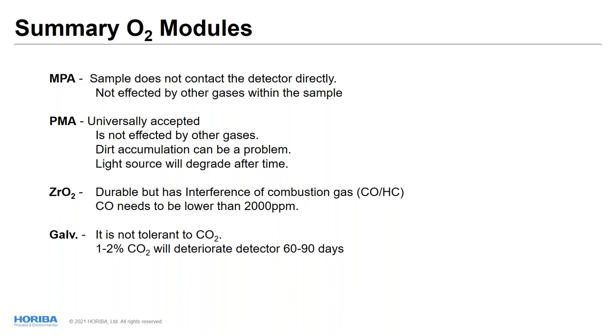The galvanic method is the lowest cost and works with a battery, so you will need to replace it periodically. It is also sensitive to CO2, and if a high concentration of CO2 exists, it will deteriorate the detector. That would be one of the weak points. So it depends on your gas composition and gas condition, and we can select the best one. But again, it's related to your budget and your gas condition, and finding the best O2 sensor is one of the keys to making your project successful.